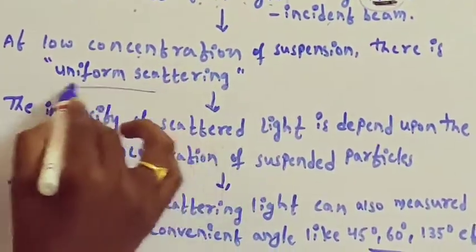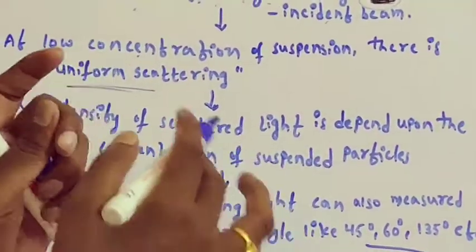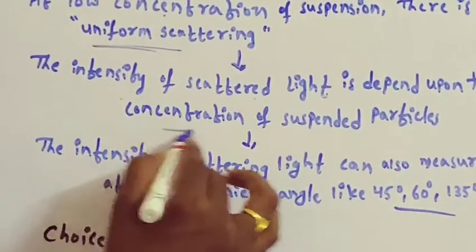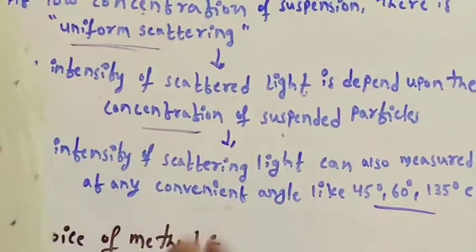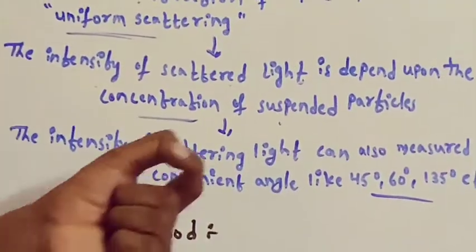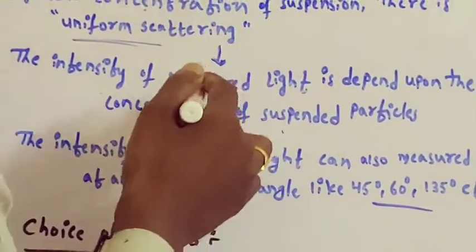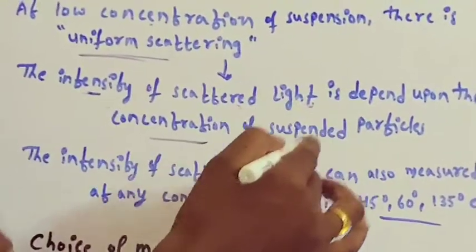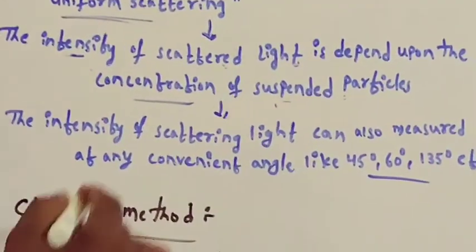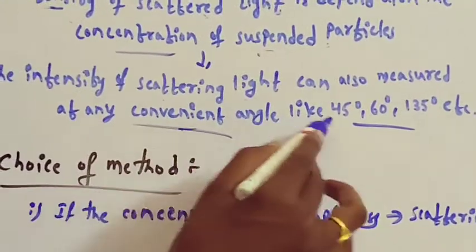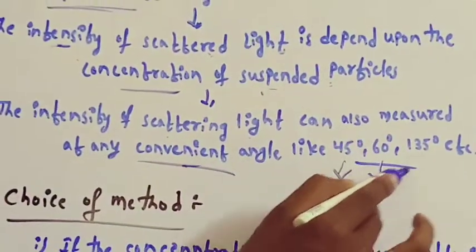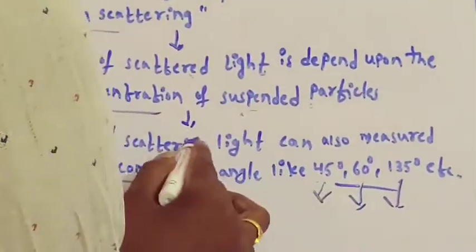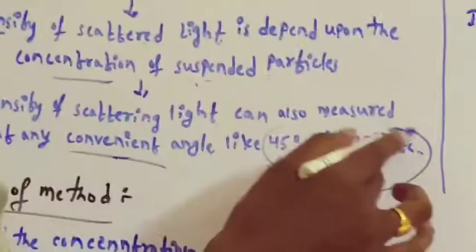At low concentration of suspension, there is uniform scattering. The intensity of scattered light depends upon the concentration of the suspended particles — more scattered light means more concentration, less scattered light means less concentration. The intensity of scattered light can also be measured at other angles like 45°, 60°, and 135°, but mainly at 90° to the incident beam.